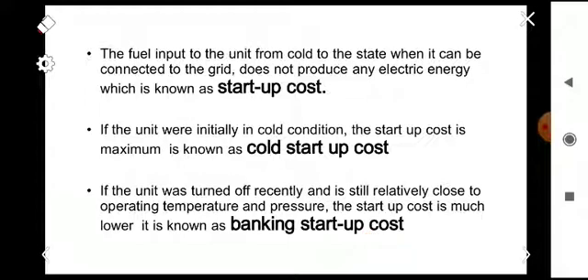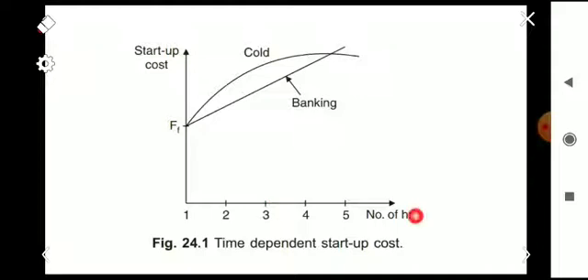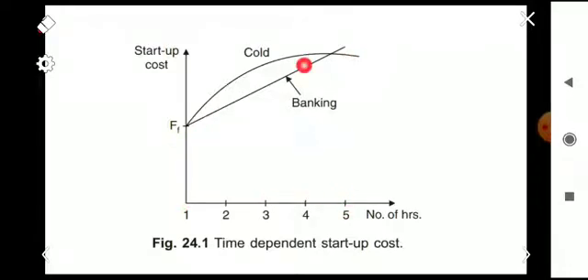If a unit was in operation and turned off recently, the machine temperature will be near the rated temperature and pressure, so the startup cost is much lower — this is called the banking startup cost. From the figure showing a curve between number of hours and startup cost, the cold start cost and the banking startup cost are compared. For a particular number of hours, the banking startup cost is very much less than the cold startup cost. That concludes the thermal unit constraint.